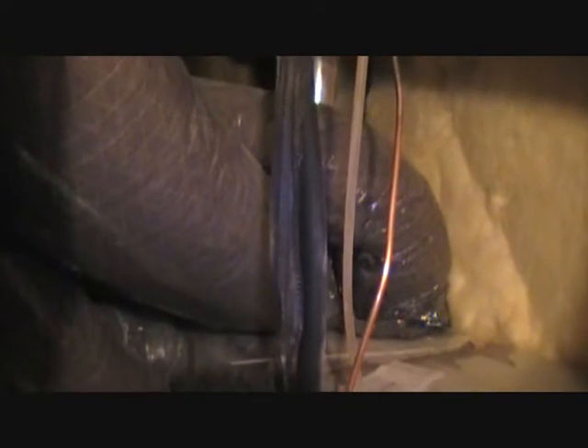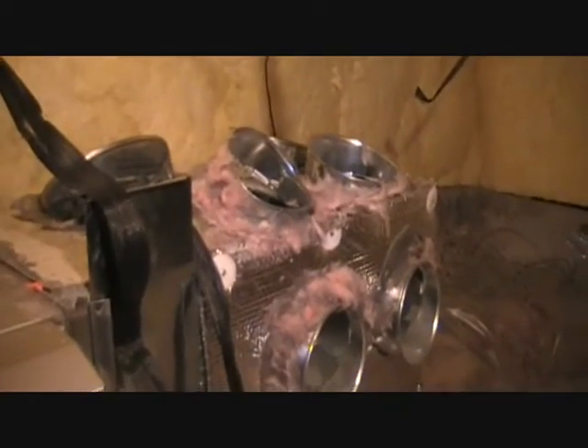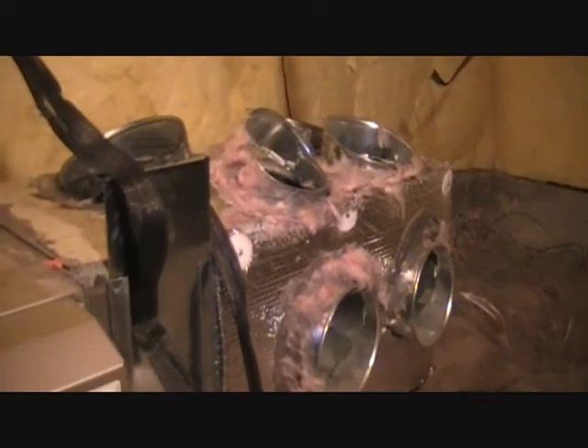Now keep in mind, this is the farthest end of the house and we're a good 40 feet in a straight line to the farthest run. Well, the farthest run doesn't run in a straight line. In fact, it's right there. I don't know how well you can see that, but it goes up from there and dips and dives several times before ever reaching the other side of the house. This is so bad, in fact, that even with all of the return air removed, we're still icing up.